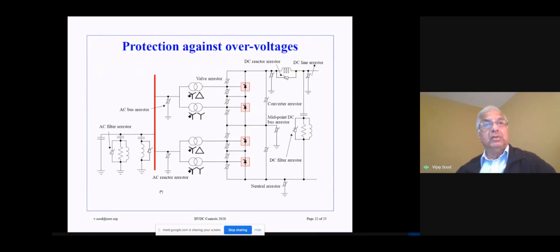For protection against overvoltages, this graphic shows you where the nonlinear voltage arresters are used to suppress any excessive voltages. So we have valve voltage arresters at various locations. Here, the filters will have their own protection. The valves will be protected against any overvoltages, so you will have surge arresters at all points. From the pole side, you will have surge arresters over there. These will be utilized for converter voltages.